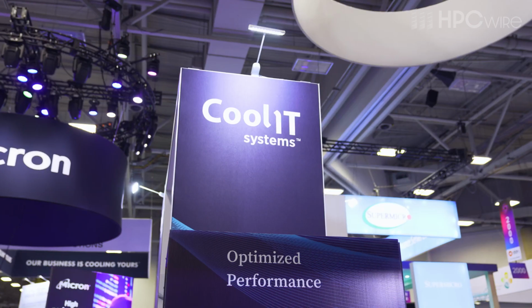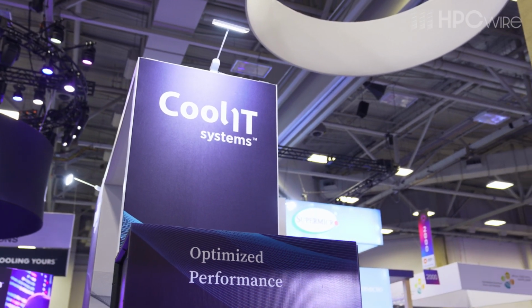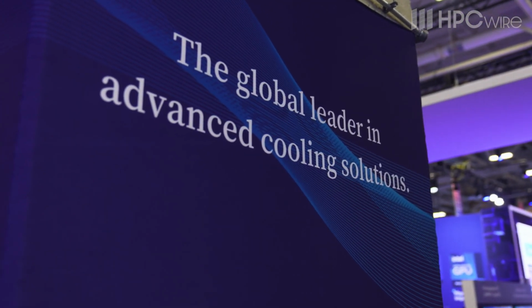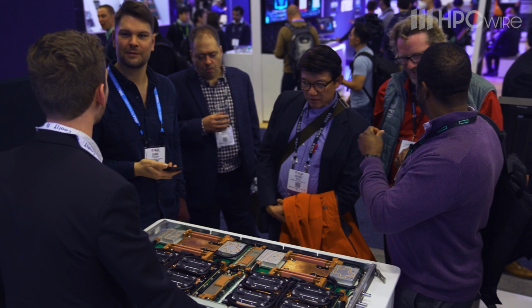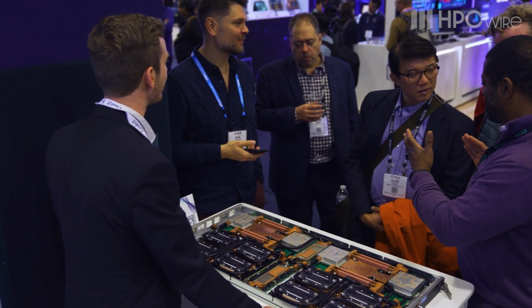Direct liquid cooling is great for sustainable data centers. We're able to reduce the cost of cooling, all the electricity used that would otherwise be going towards a chiller to get cold water and running the fans in servers. We can reduce the electricity required for those applications because direct liquid cooling is a more efficient means of cooling servers.